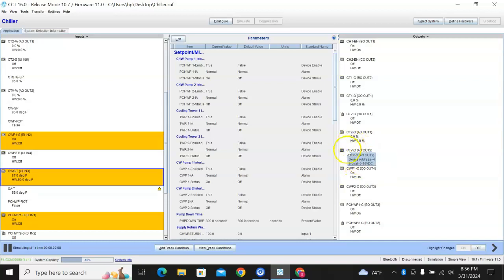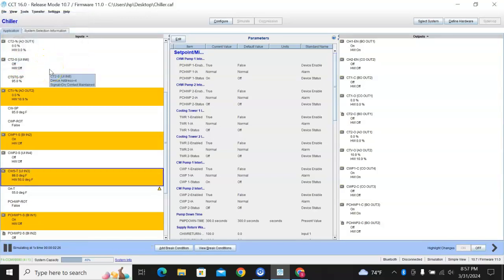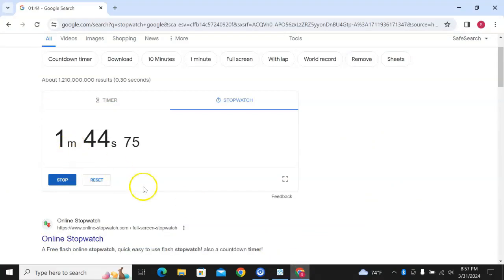Still haven't moved on the bypass yet. There we go. Slowly starting to move. We're at 10, right? So basically 10% is going over the top of the tower. I'll go ahead and do 88. Because where I'm at down in Texas, it gets warm outside and you'll see condenser water temperatures move this quickly, especially if we're not going over the top of the tower. Fans aren't turned on. Going to check the time. 1 minute and 44 seconds.